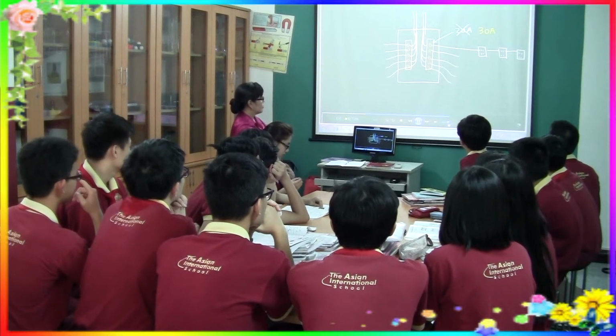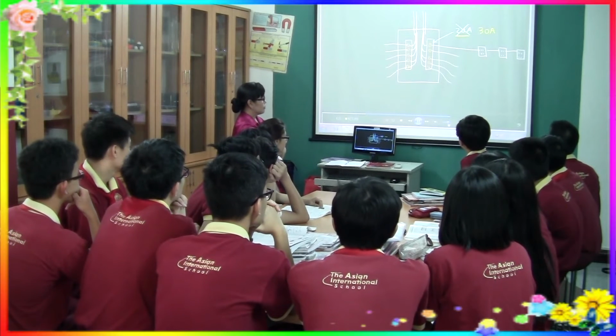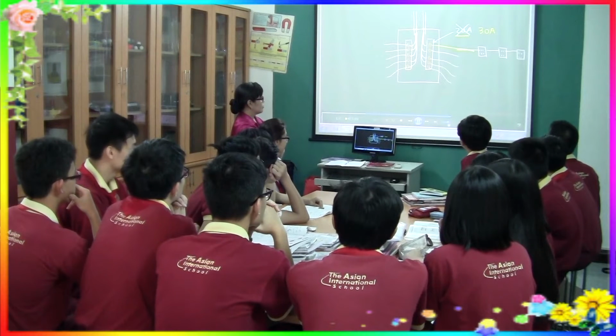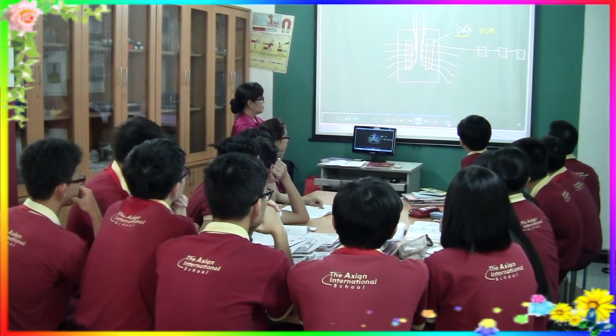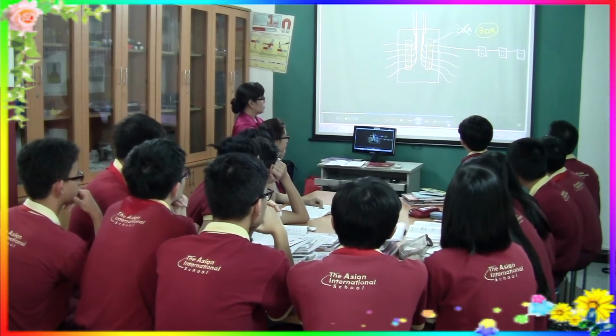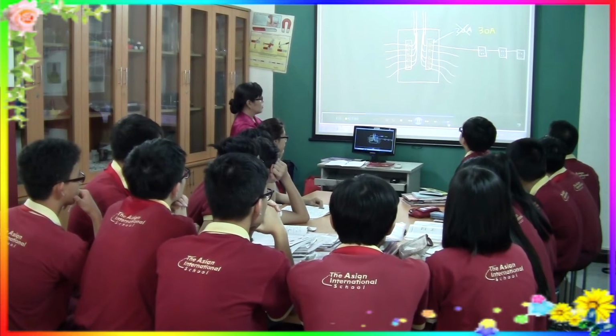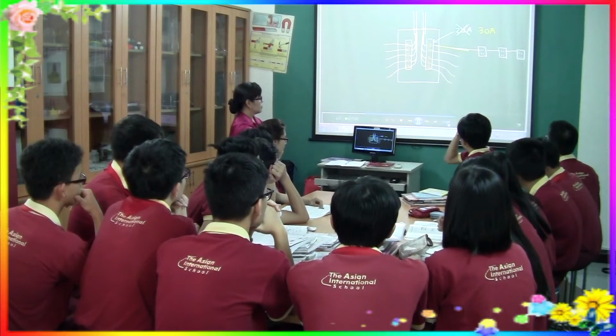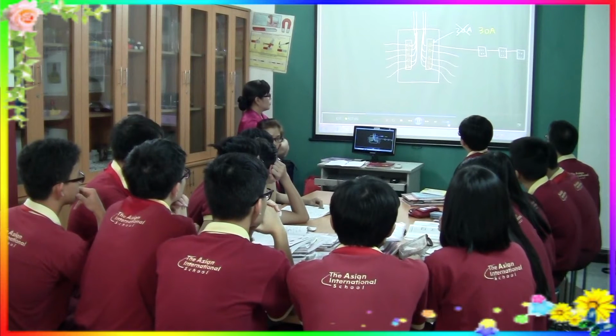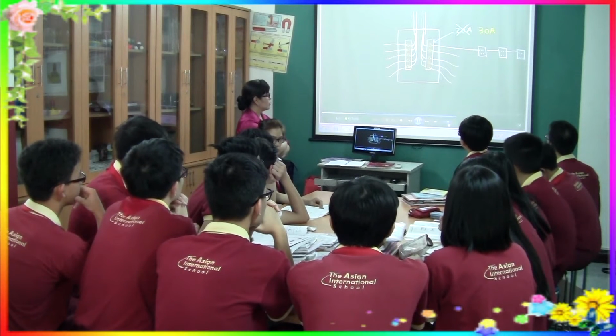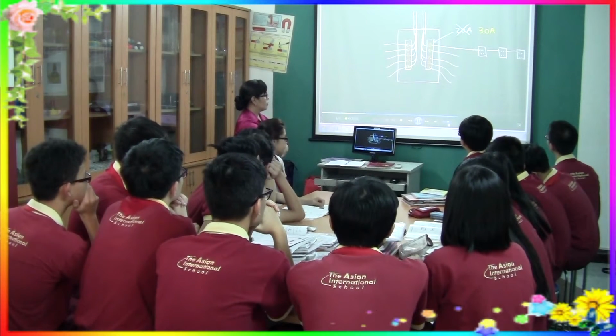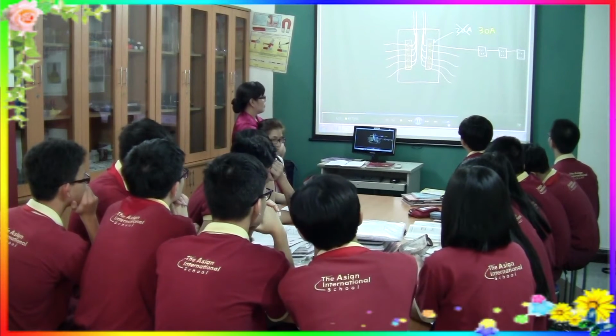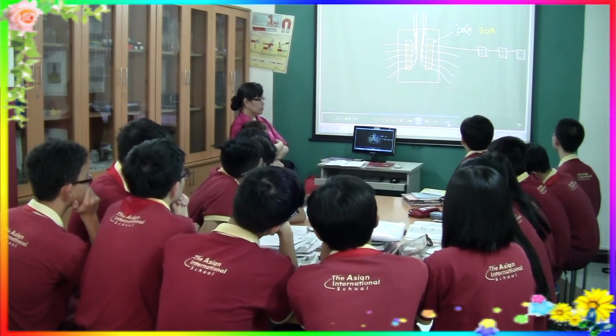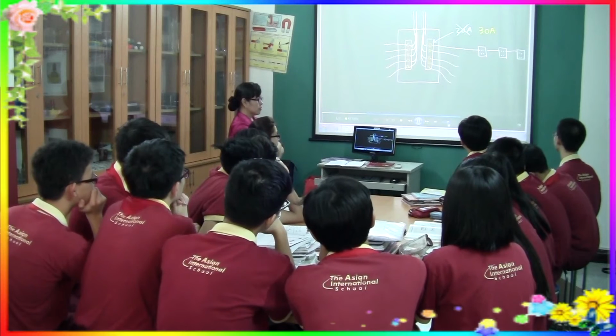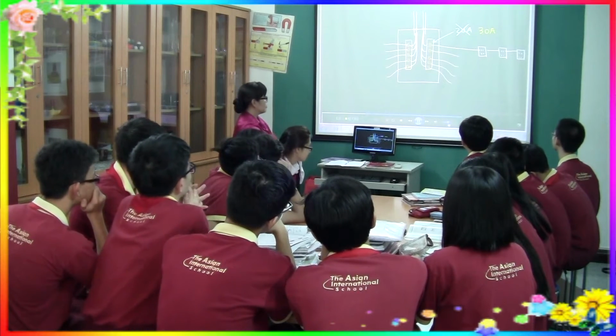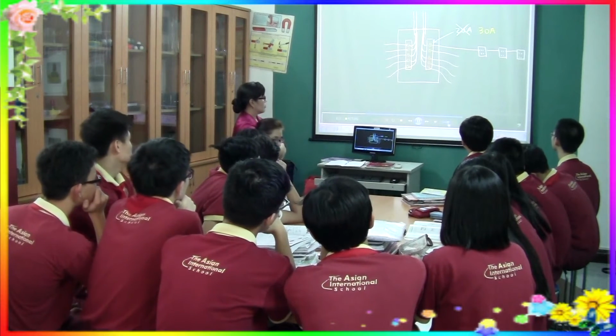That's bad. The reason there was a 20 amp fuse here is because this wire isn't supposed to carry more than 20 amps. If you replace the 20 amp fuse with a 30 amp fuse, you're allowing more electricity to flow through the wire than it was designed to handle, and that's the kind of thing that typically starts a fire. People replace the fuse with one that's the wrong size or amperage, allowing too much electricity and heat to be generated, and a fire gets started.